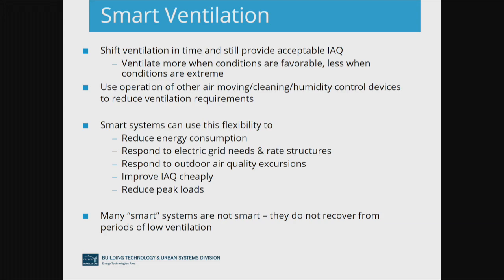Smart ventilation is a generic term for the idea that since we're not ventilating for acute events but thinking about long-term exposures to contaminants or long-term moisture buildup, we can move when we ventilate around in time. If I'm looking at your cumulative exposure to some contaminant over a year, we can ventilate less at times when we'd be exposed to higher concentrations, but ventilate more at other times with lower concentrations, so the total for the year stays about the same. That's smart ventilation: moving when ventilation happens around in time.